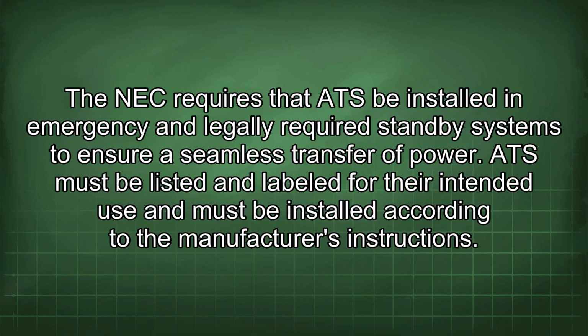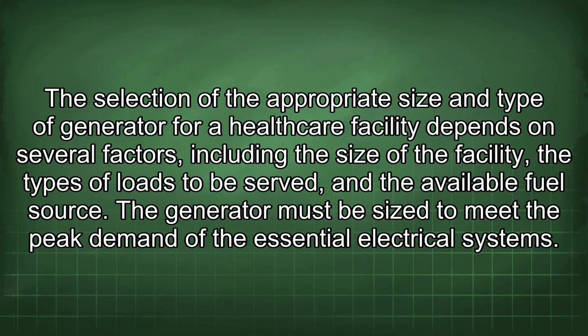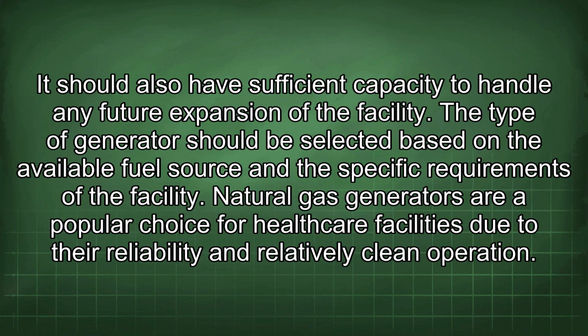ATS must be listed and labeled for their intended use and must be installed according to the manufacturer's instructions. The selection of the appropriate size and type of generator for a healthcare facility depends on several factors, including the size of the facility, the types of loads to be served, and the available fuel source. The generator must be sized to meet the peak demand of the essential electrical systems. It should also have sufficient capacity to handle any future expansion of the facility.